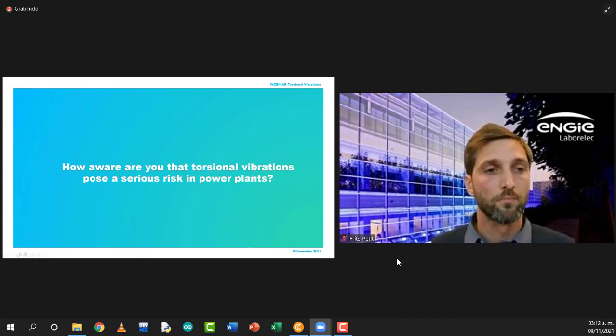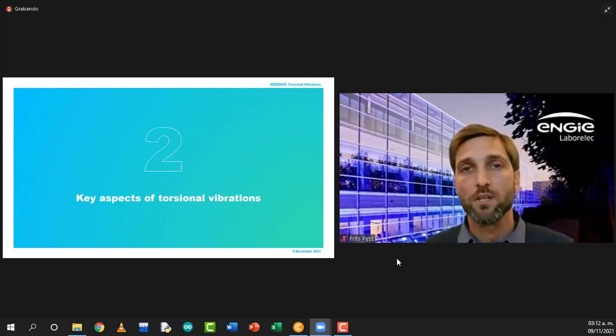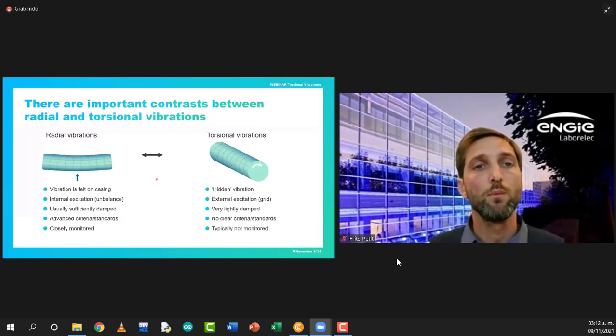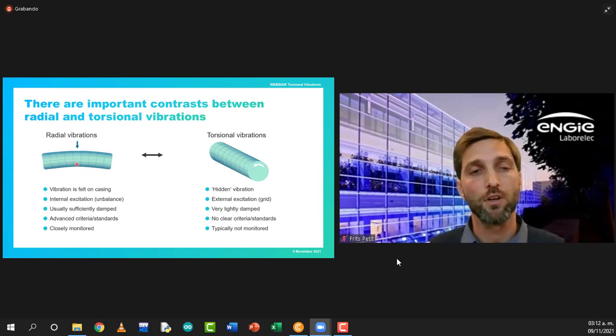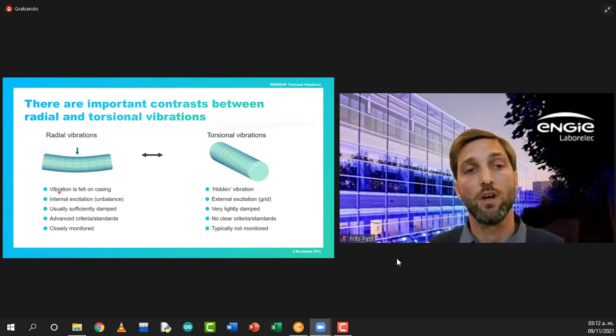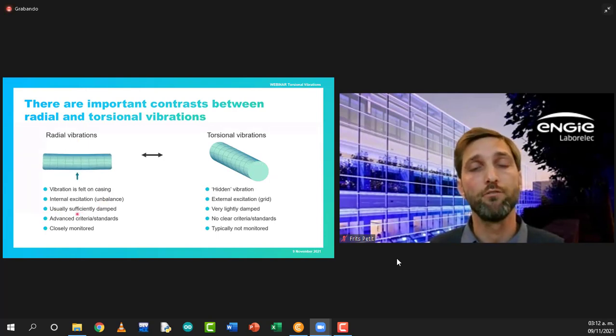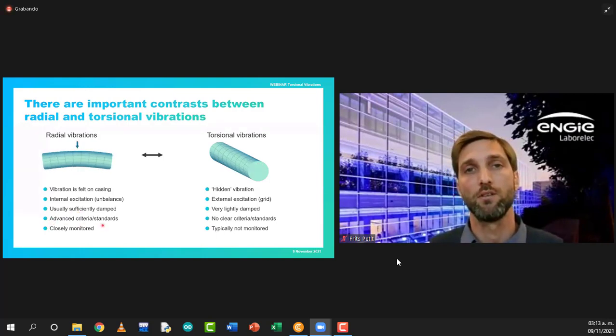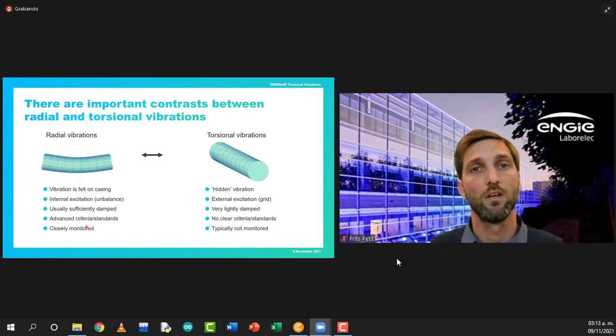So let's move on. Now let's go to the key aspects of torsional vibrations, so the basics. Most people are more familiar with radial vibrations. This is the vibration in the horizontal and vertical framework of your shaft line. This is a vibration which is felt on the casing. The excitation is typically due to unbalance. It's usually sufficiently damped, and your bearings provide some damping due to the oil. We have advanced criteria and standards. It's also closely monitored, so every shaft line typically has a radial vibration monitoring and/or protection system. And people are well aware of the risk that radial vibrations can introduce.